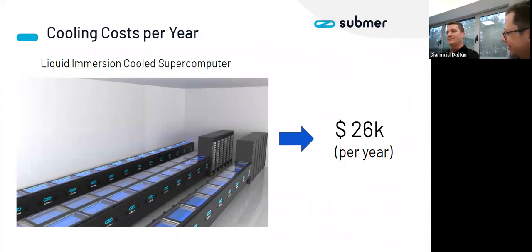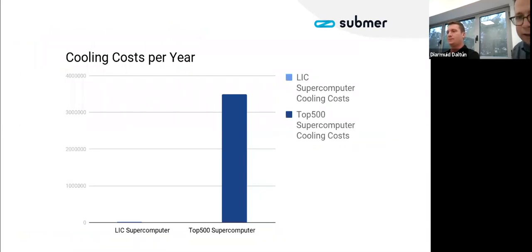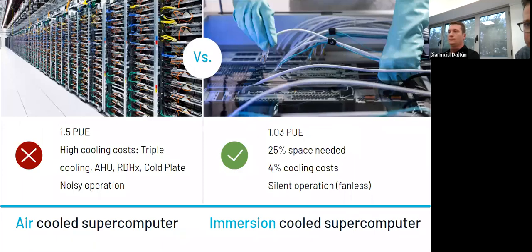And is this a joke? Well, this is essentially the difference between a PUE of around 1.5 and a PUE of 1.03, which is what we'll typically see in a full installation, obviously accounting for the dry coolers and the pumping systems. Yeah, I think Matteo put together this graph, but I think we already got that the difference is huge. Yeah, I mean, this is obviously very visual regarding the costs, the operating costs for energy on the cooling. Indeed. So resuming, there's that challenge, that main difference there with the PUE between one system and another.